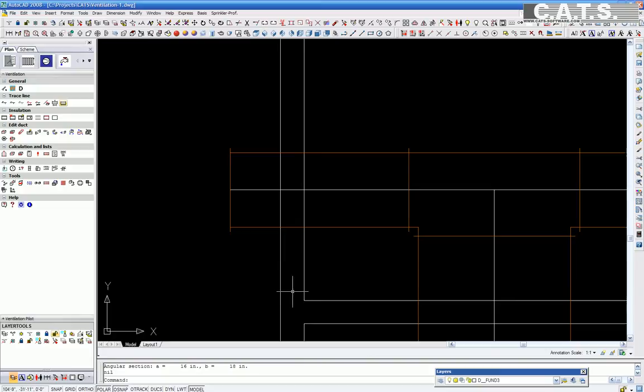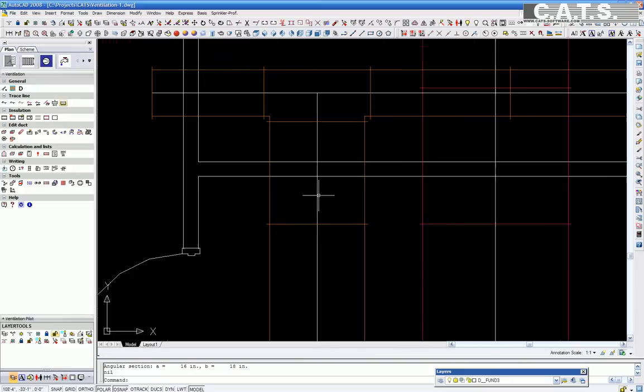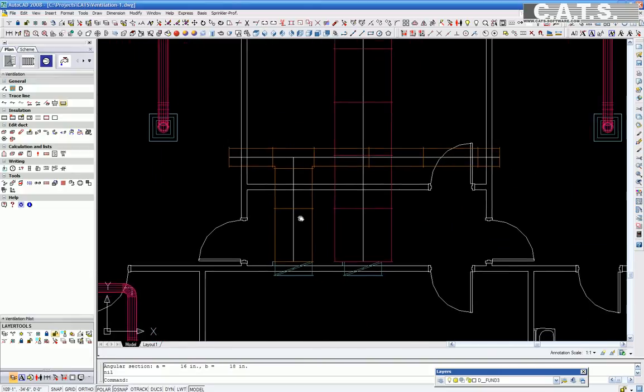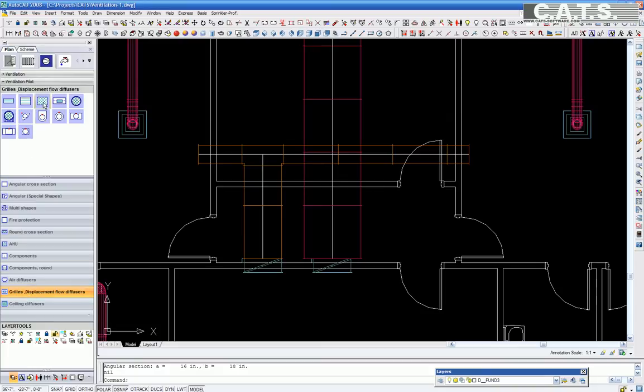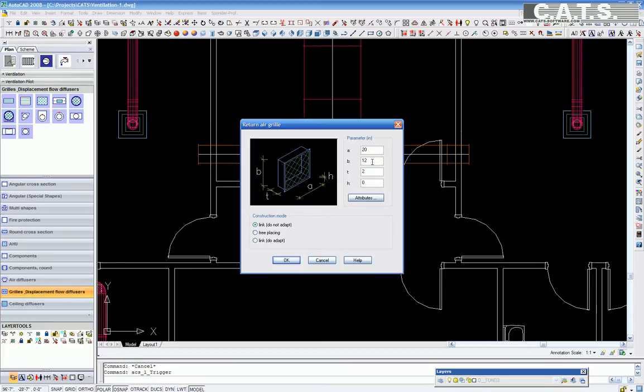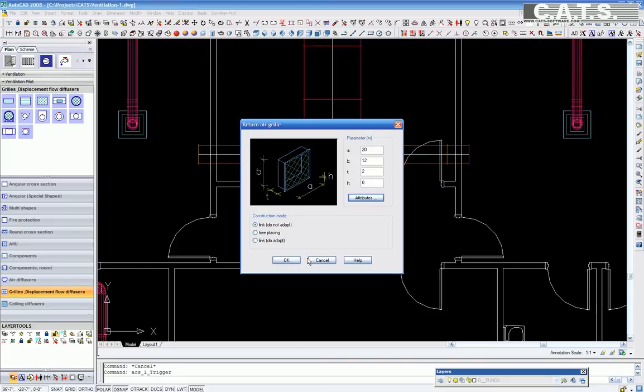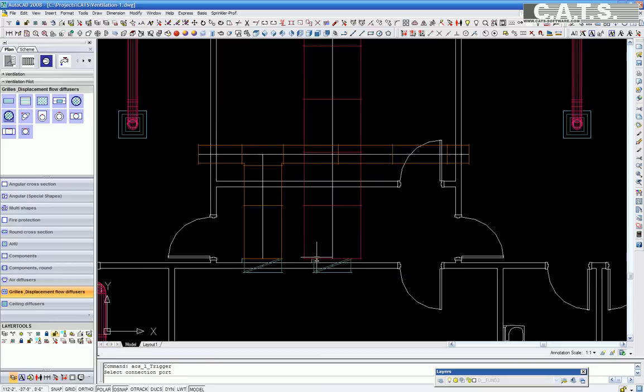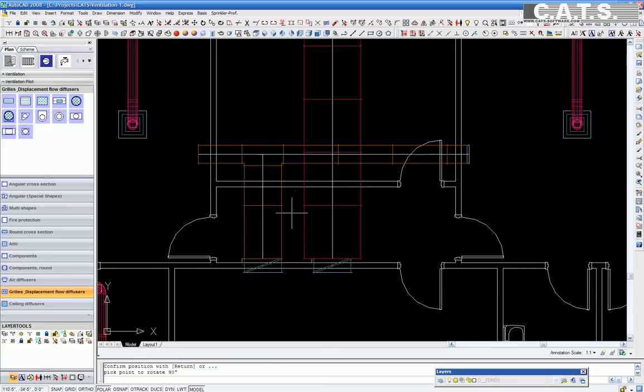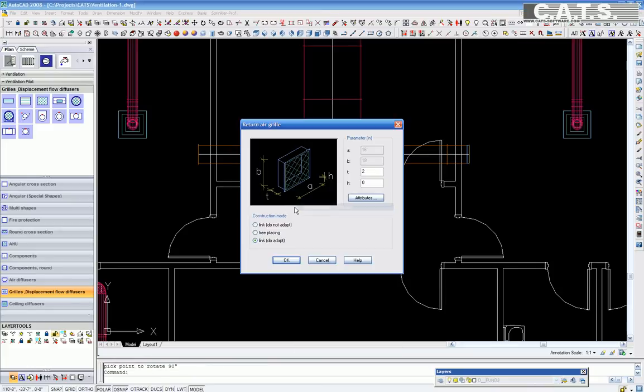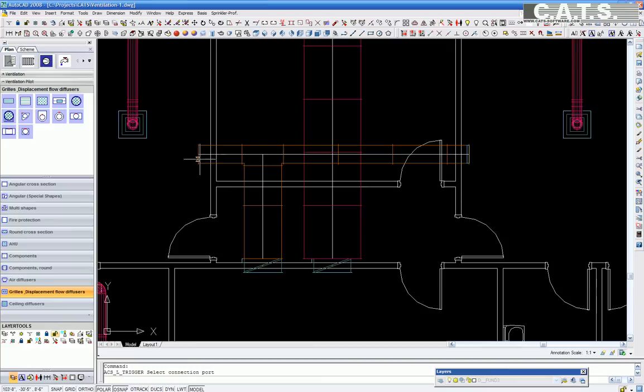In the CATS Commander, we will now select a return air register for the duct opening. In Attributes, for the return air grill, we will revise the value to 1200 CFM. Select OK. You will then select the type of connection to connect the return duct. Select Link. Select OK. Select the end of the duct to place the return grill. The flexible management layer appears, prompting us to select the layer for this component. Repeat the procedure for the other side of the return.